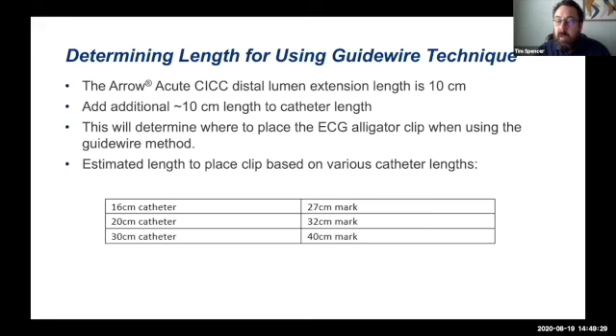stating that if you do have a 16 centimeter catheter, the alligator clip is going to go on at the 27 centimeter mark. If it's a 20 centimeter catheter, at the 32 centimeter mark, or if it's a 30 centimeter catheter, at the 40 centimeter mark. But don't just take my word for it. Measure it yourself. That's a very important strategy that every clinician needs to do when utilizing a guide wire technique, making sure they've got an accurate measurement of the wire.